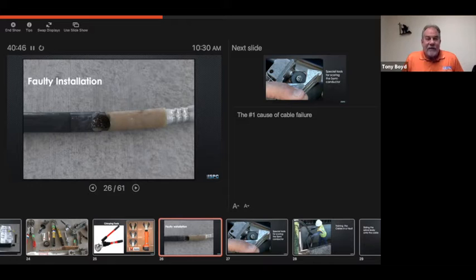So when he was getting the semiconductor shield off, which is right here, his knife actually cut into the insulation just a little bit. So when we energized it, one year later, to the very month, is where this blew off. So basically, it was brand new. We energized it. There was hardly any load.